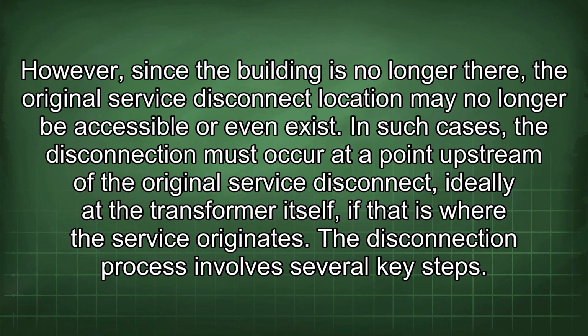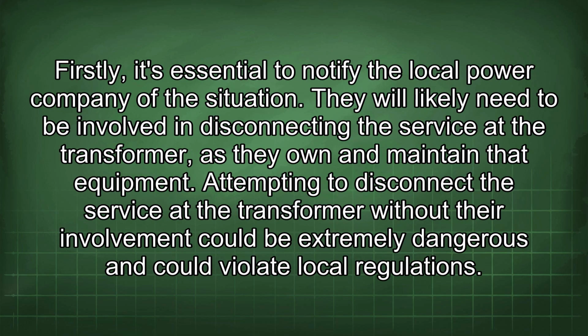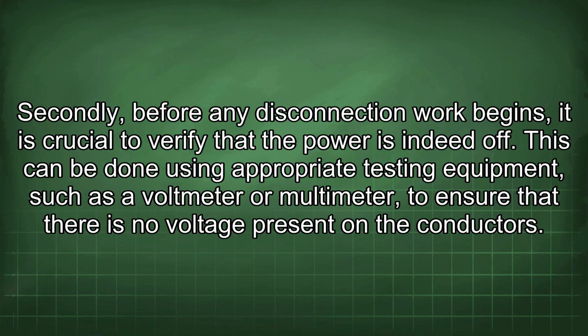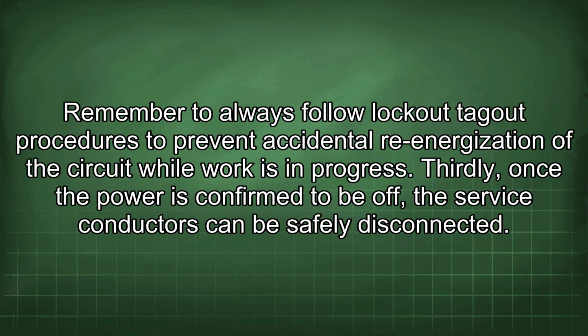The disconnection process involves several key steps. Firstly, it's essential to notify the local power company of the situation. They will likely need to be involved in disconnecting the service at the transformer, as they own and maintain that equipment. Attempting to disconnect the service at the transformer without their involvement could be extremely dangerous and could violate local regulations. Secondly, before any disconnection work begins, it is crucial to verify that the power is indeed off. This can be done using appropriate testing equipment, such as a voltmeter or multimeter, to ensure that there is no voltage present on the conductors. Remember to always follow lockout-tagout procedures to prevent accidental re-energization of the circuit while work is in progress.